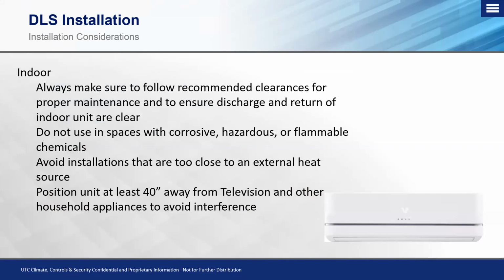We want to make sure that we're not using these indoor units in spaces with corrosive, hazardous, or flammable chemicals. We want to avoid installations that are too close to an external heat source, such as placing a unit behind the backside of a refrigerator, where radiant heat can hit the return air sensor and cause the unit to shut off prematurely. We also want to position the unit at least 40 inches away from any smart enabled devices, such as smart TVs or other smart appliances around the home, to make sure we're not going to run into any signal interference on our S or signal wire.